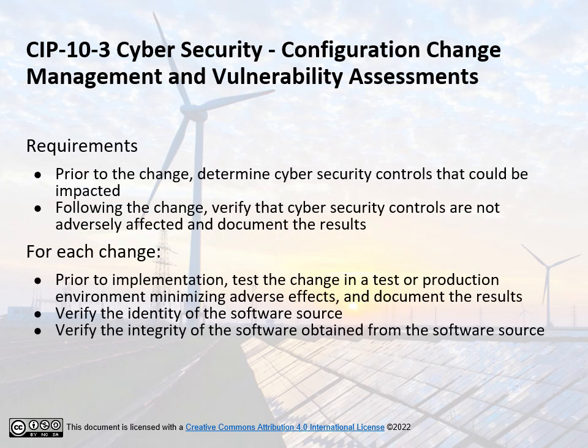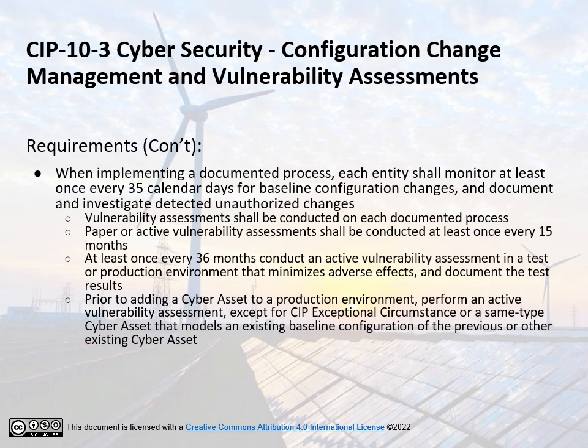CIP-010-3 Configuration Change Management Vulnerability Assessment. Requirements: prior to the change, determine cybersecurity controls that could be impacted. Following the change, verify that cybersecurity controls are not adversely affected and document the results. For each change, prior to implementation, test the change in a test or production environment, minimizing adverse effects, and document the results. Verify the identity of the software source. Verify the integrity of the software obtained from the software source.